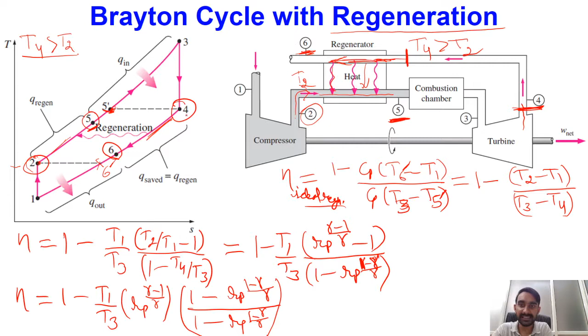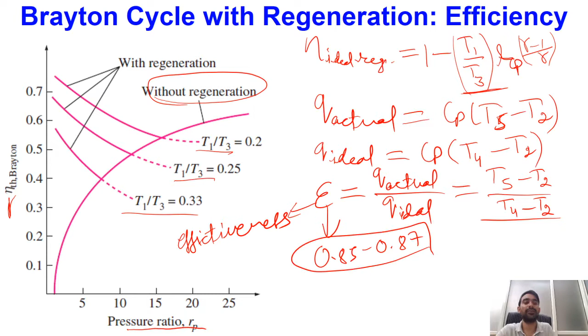So we define a factor of heat exchanger performance, or regenerator performance, and we call that factor epsilon, which is known as the effectiveness of the regenerator or effectiveness of the heat exchanger. This is equal to Q actual divided by Q ideal, and ultimately we find its value as T5 minus T2 divided by T4 minus T2. Here T4 minus T2 corresponds to the maximum possible, and T5 minus T2 is for the actual one. Because we cannot always achieve 100% efficiency, for practical values the effectiveness of a typical regenerator is kept close to 0.85 to 0.87. So this is for the general Brayton cycle based regeneration system.